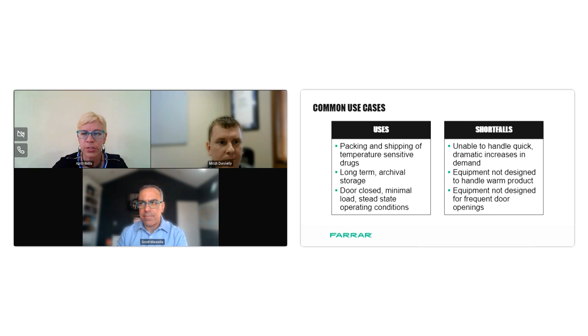Thank you. And I know that in addition to equipment failures, temperature excursions can be a big problem for the industry. What kinds of activities lead to temperature excursions? Yeah, so typically your freezer can just fail. I mean, obviously all equipment has the ability to just have some type of reliability problem with it. But usually it coming back to if you're opening the door more frequently or not allowing the freezer to recover from those door openings, or it takes too long to recover, when you put warm product into it, that will typically take your freezer or refrigerator out of whatever temperature range it was meant to be set at until it's able to pull back down into the correct operating point.